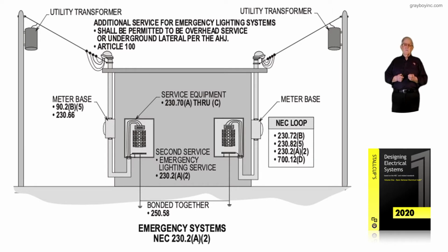And then notice 230.2(A)(2) recognizes that we could have an additional service to serve as an emergency system in accordance with 700.12(D), as in dog.